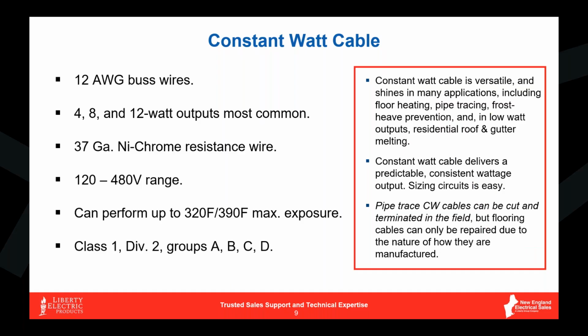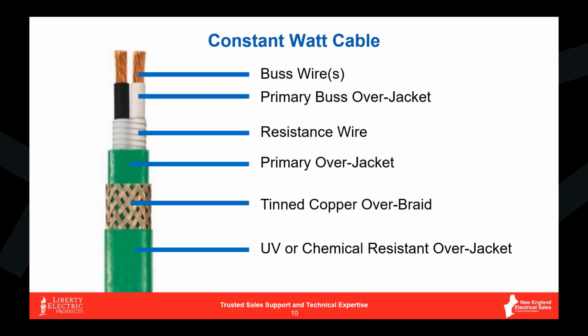The other thing is that obviously with nothing there to put the brakes on the heat output of a cable like this, they are not recommended for use with PVC or CPVC piping systems.